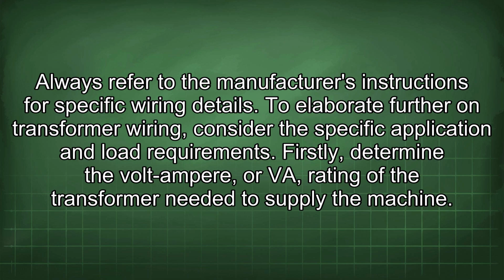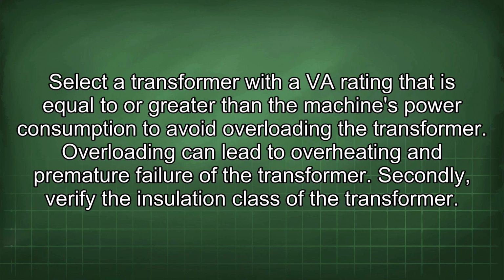To elaborate further on transformer wiring, consider the specific application and load requirements. Firstly, determine the volt-ampere, or VA, rating of the transformer needed to supply the machine. Select a transformer with a VA rating that is equal to or greater than the machine's power consumption to avoid overloading the transformer. Overloading can lead to overheating and premature failure of the transformer.